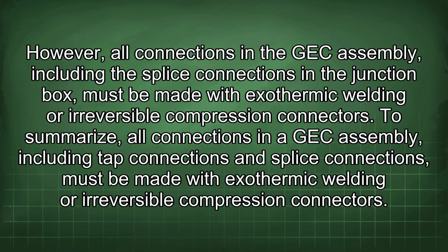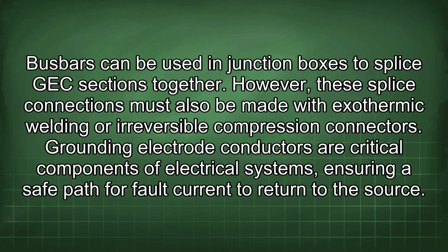However, all connections in the GEC assembly, including the splice connections in the junction box, must be made with exothermic welding or irreversible compression connectors. To summarize, all connections in the GEC assembly, including tap connections and splice connections, must be made with exothermic welding or irreversible compression connectors. Busbars can be used in junction boxes to splice GEC sections together. However, these splice connections must also be made with exothermic welding or irreversible compression connectors.